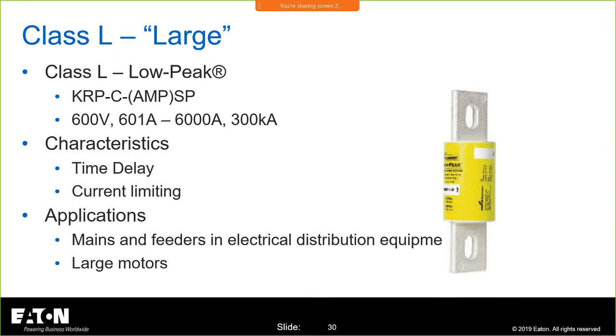All right, I'm going to take a look on YouTube and see what kind of questions the tubers out there have going on. Luis Diego: I've always asked myself why the dual-element fuse on transformers crosses the damage curve of the transformer, and that's how it is recommended. Yes, remember, it will cross the transformer damage curve, and I might plot one of those. I'm going to save that for a little bit later.